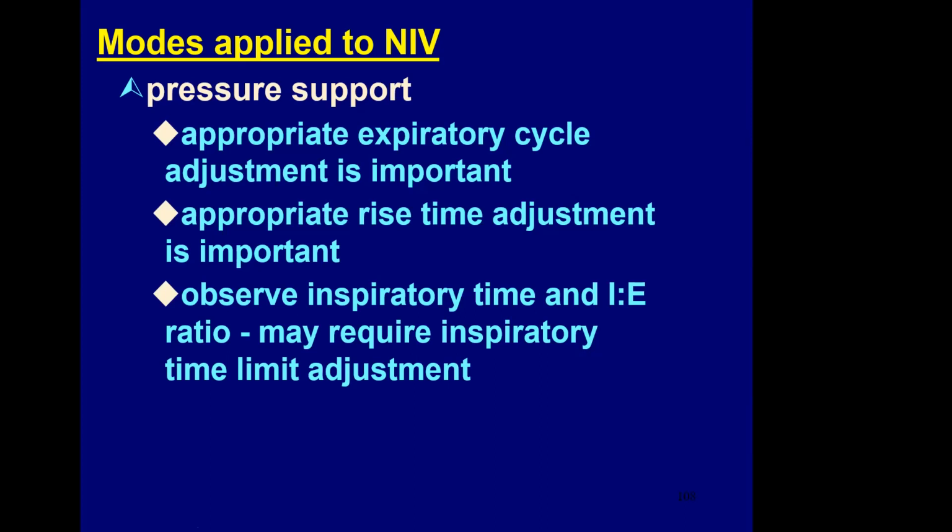Also, an appropriate rise time adjustment is important, and we must observe the inspiratory time and I:E ratio, which will require us to adjust the inspiratory time limit.